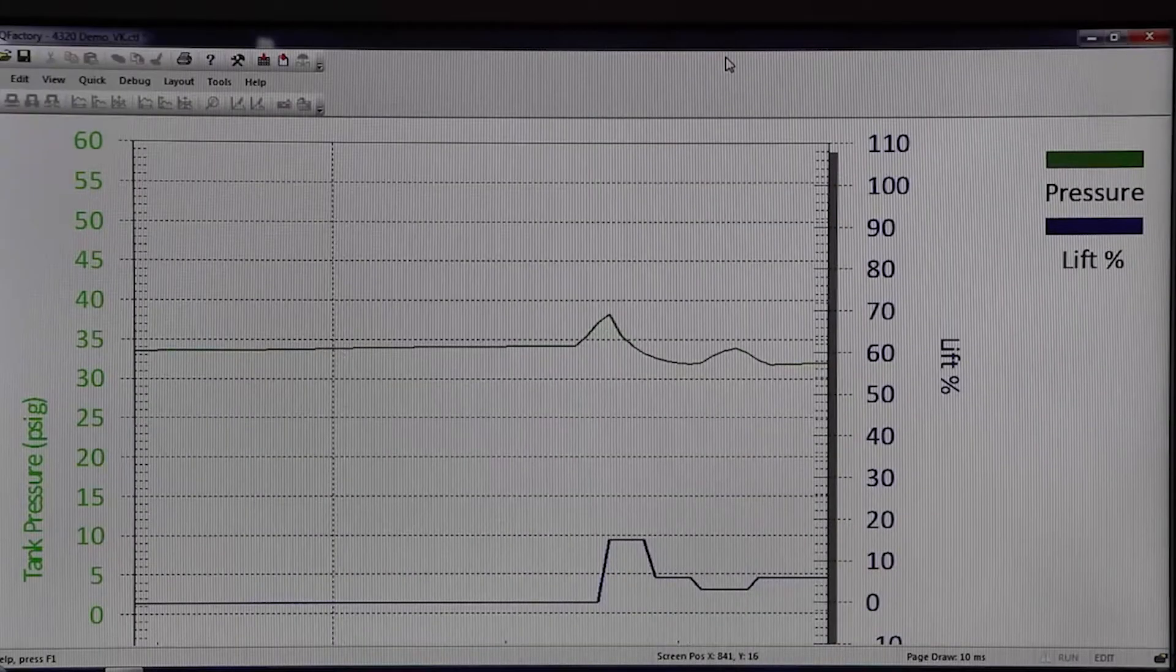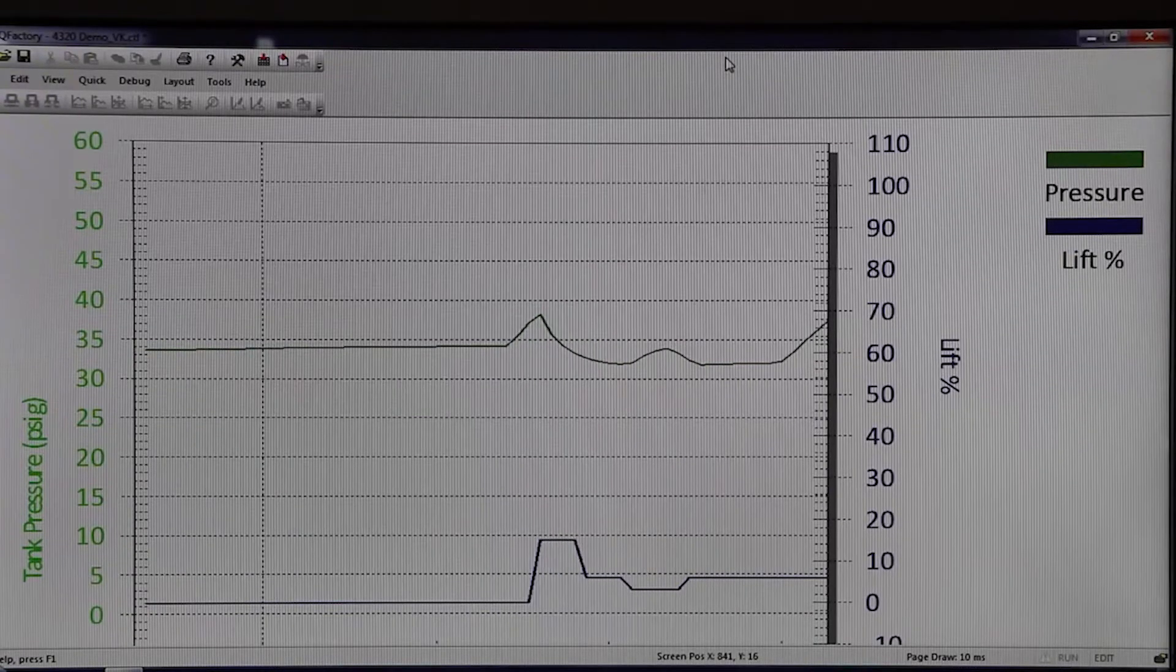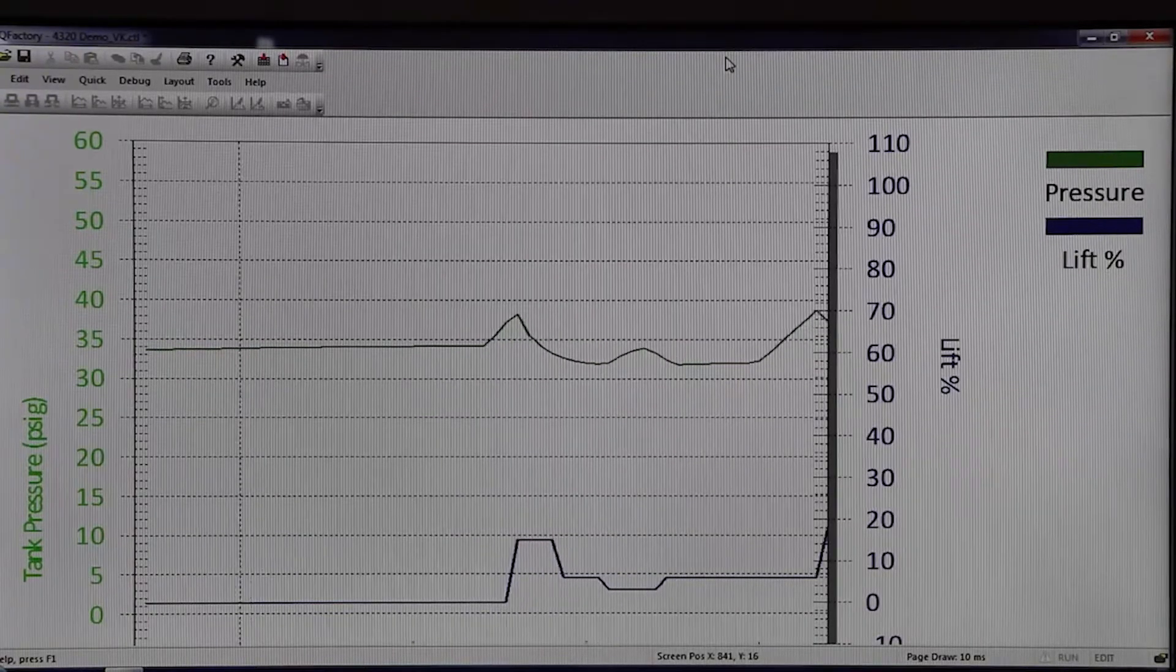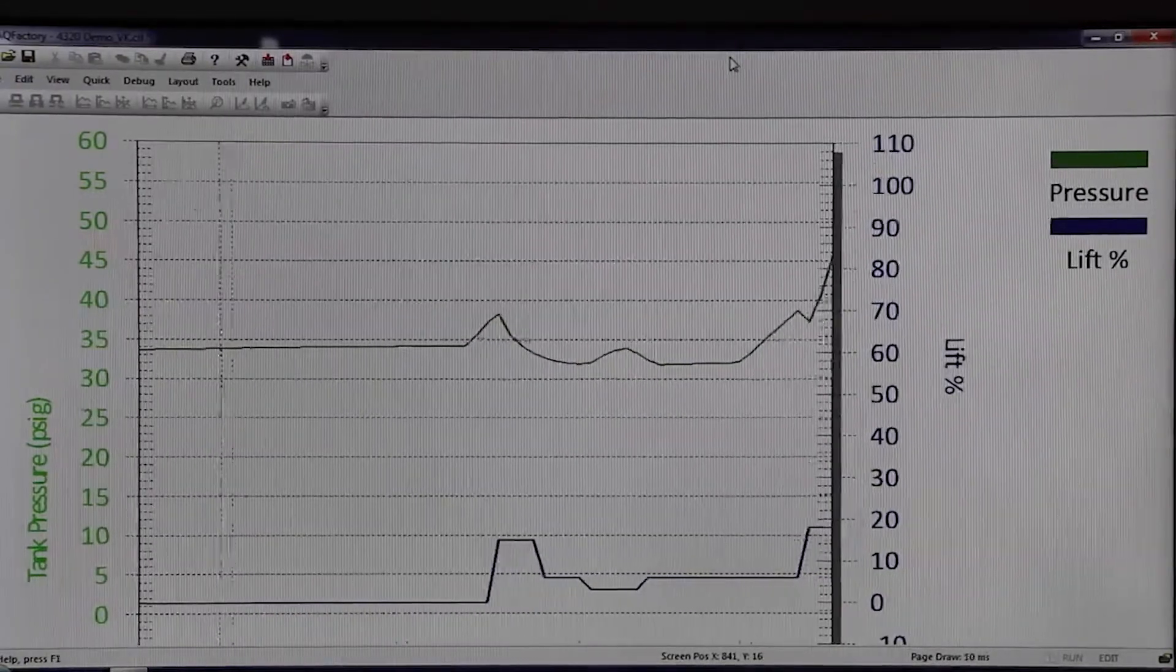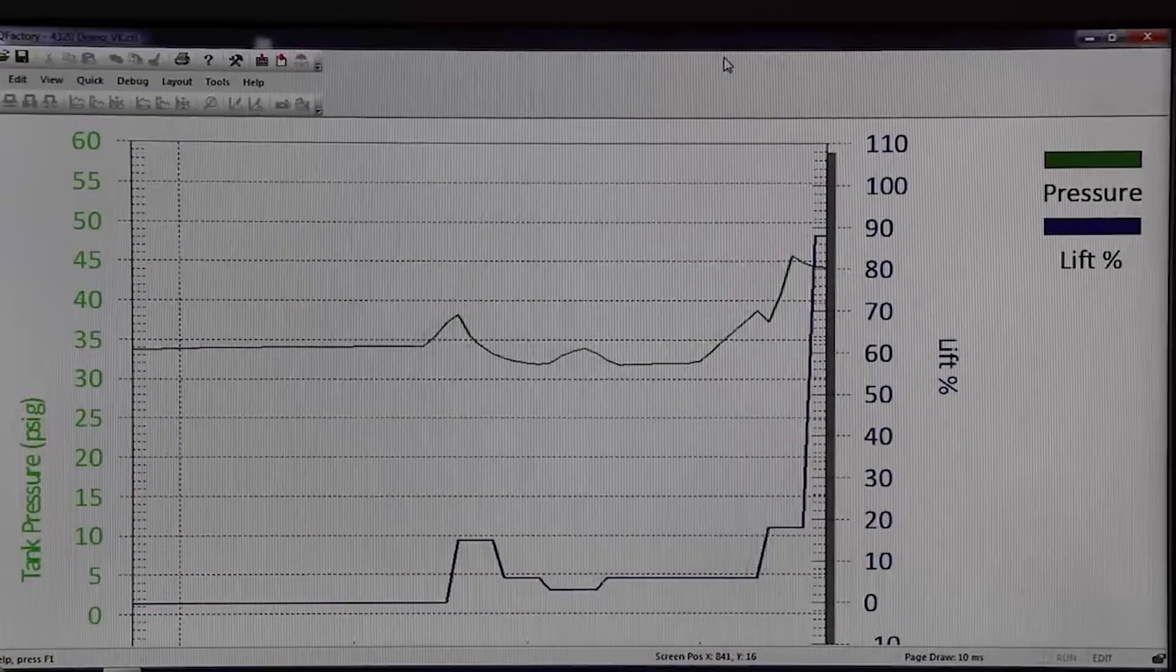In this example, we will illustrate a valve that is simmering. In an overpressure event, fluid being relieved with an inlet static pressure below the pressure relief valve's popping pressure with no measurable capacity is considered simmering.